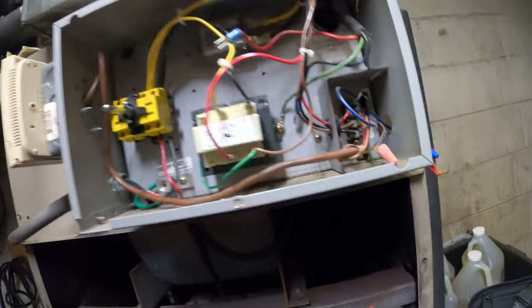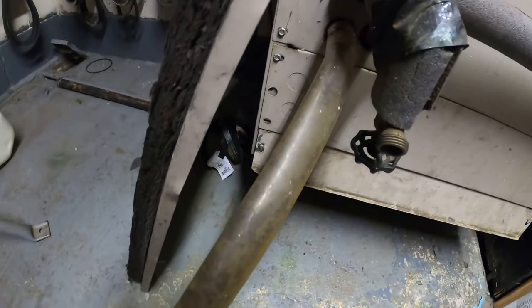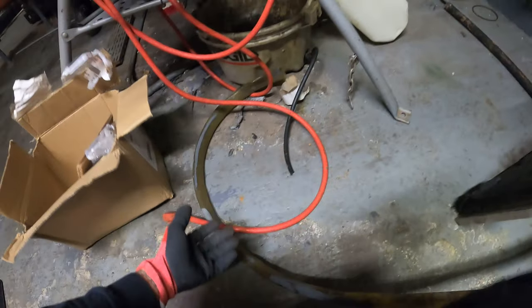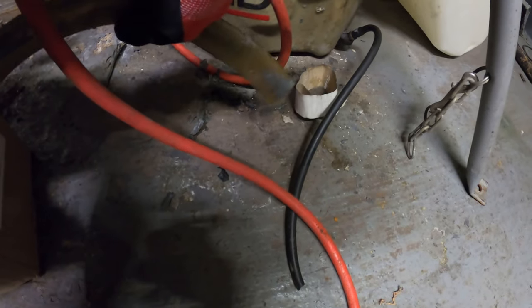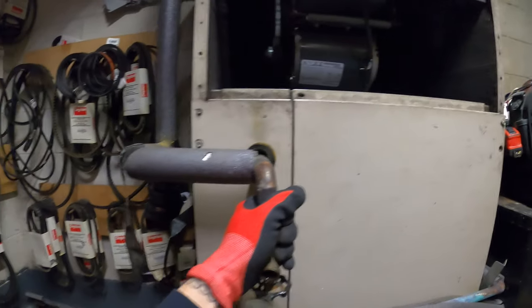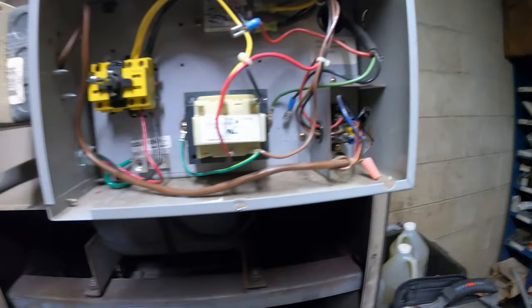It's just a mess. Look at this — that's not good. Here's the actuator — that's the actuator for the water. And look at this drain — what is that? Look where it's draining to — there's water in there. This actuator must be just propped open. This thing is stuck open. There are a lot of things wrong here and this thing is ancient. We're going to rebuild this nicely, but let's just get it working first because I need to get approval for those repairs.